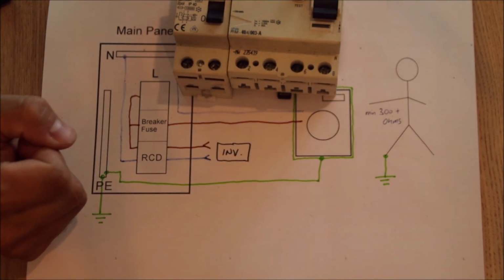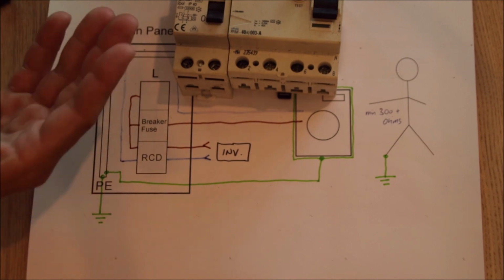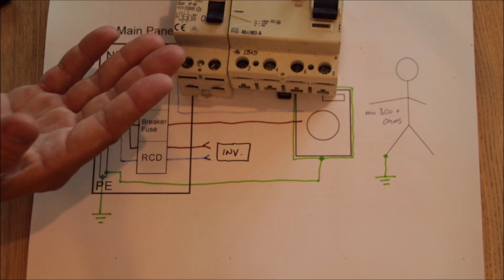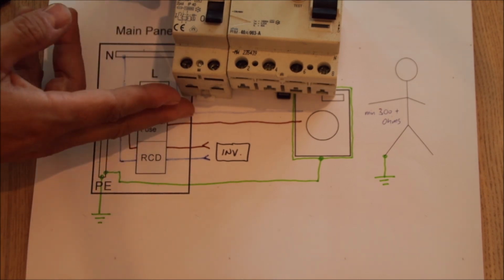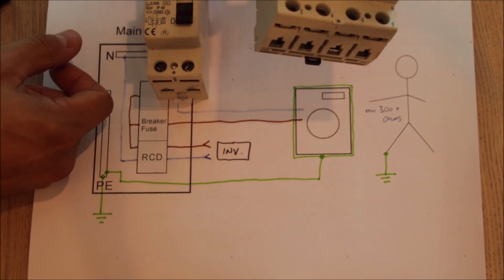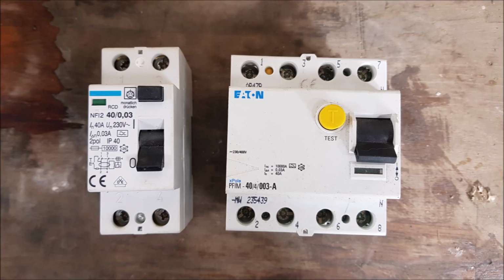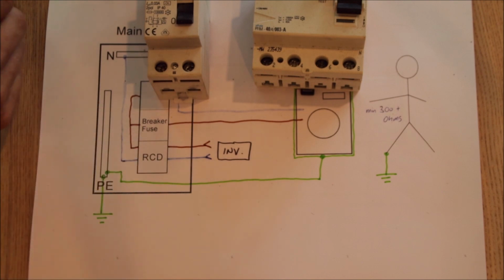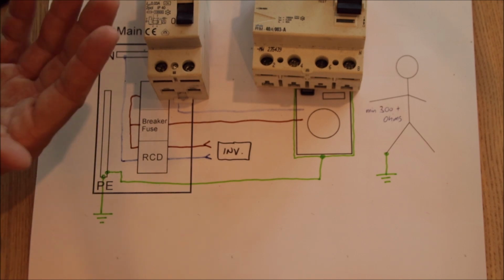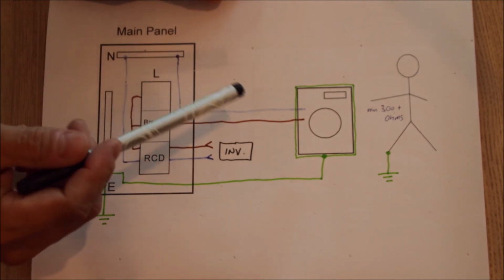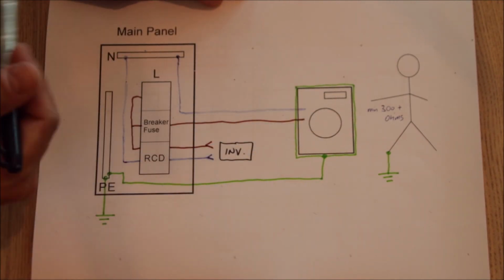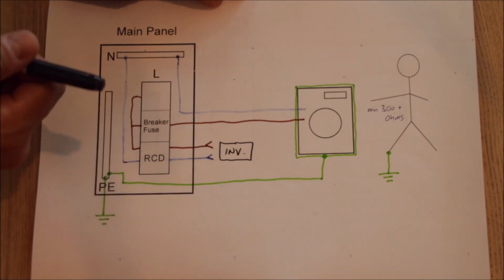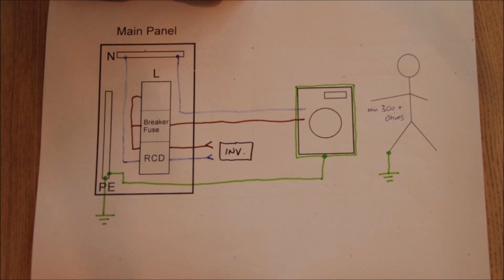And then the second and the most important group, because this is the group which is actually the heart of the earthing system, and this is the RCDs. In this case, a single pole RCD. This one would be a three-phase RCD. How the RCDs in United States look like, which are used in those boxes there, I don't know. This is an example for a DIN rail system. But of course, the features and the functionality is the same. And then the last component is whatever we use as an appliance on our system. Can be devices like washing machines, air conditioners, lights, freezers, you name it, whatever the case may be.